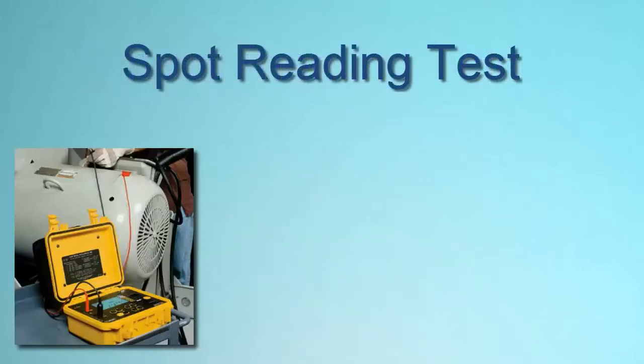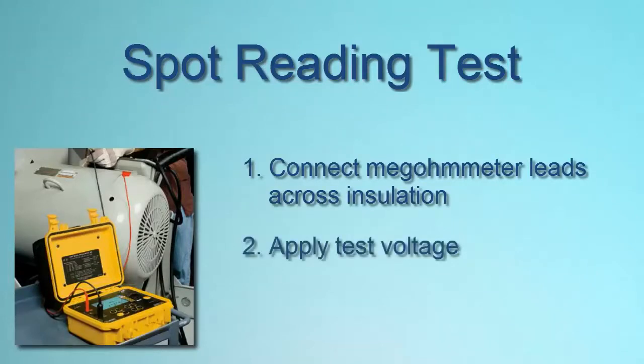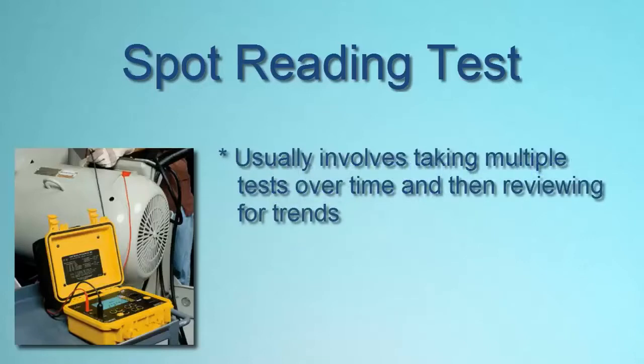The first type of insulation resistance test we'll look at is the spot reading test. This is relatively straightforward — simply connect the megohmmeter leads across the insulation to be tested, apply test voltage for a fixed period of time, typically 1 to 10 minutes, and then take a resistance reading. Spot testing is suitable for a system with small or negligible capacitive effect, for example a short wiring run. A single spot reading test is of limited value, but the results become meaningful when a series of tests — all featuring the same voltage and duration — are performed over time and the results compared.